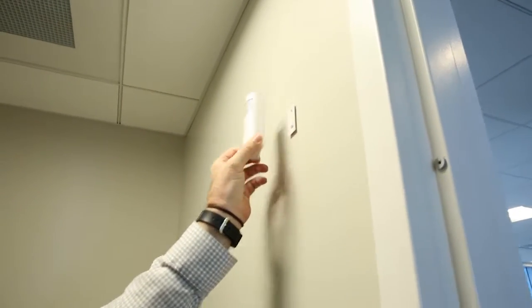Want to come in? I want to show you guys this. To date, we haven't had any occupancy sensors, but we have an occupancy sensor here. This is going to control motion. One of the things you can always do from a testing standpoint, when somebody says, hey, my sensor's not working: it could be the battery is off, this thing is broken, it's not getting a wireless connection back to the device, or the programming's gone bad. There are a lot of things that can go wrong, but you can test it very easily here.